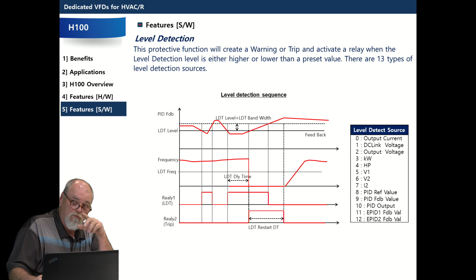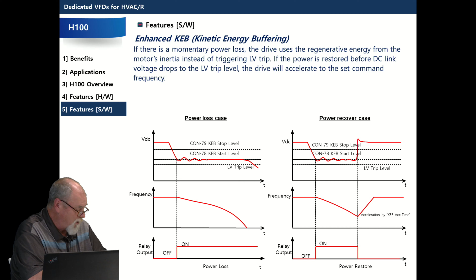This is a nice function, what we call kinetic energy buffering. We had to prove it out in North Carolina. But what it does, instead of faulting when you have a brownout condition, the drive can actually try to absorb the regenerative energy and try to ride through the brownout instead of tripping and shutting down. We had to meet an 8-second brownout, and we did. Brought it right back up online. It was at a textile facility. Most of the time when you see my competitors, they talk about milliseconds on a brownout condition. But with our kinetic energy buffering, we can ride out for a longer period of time. I'll talk about multi-motor in a little bit.